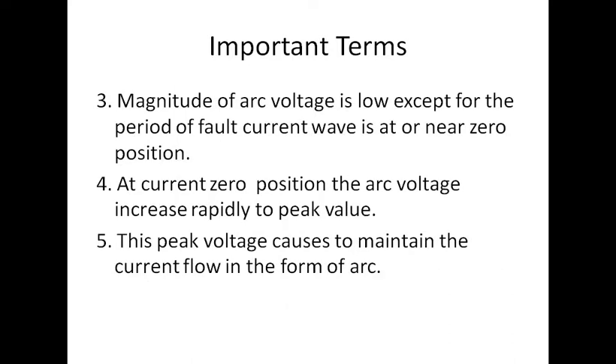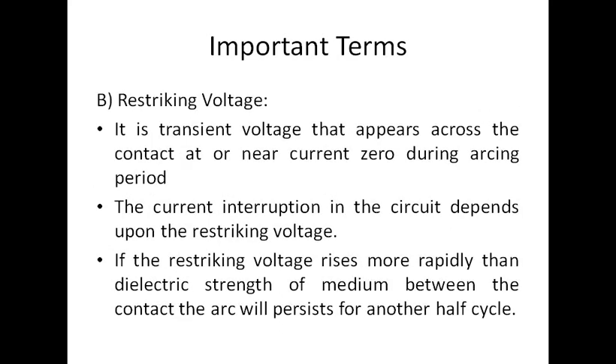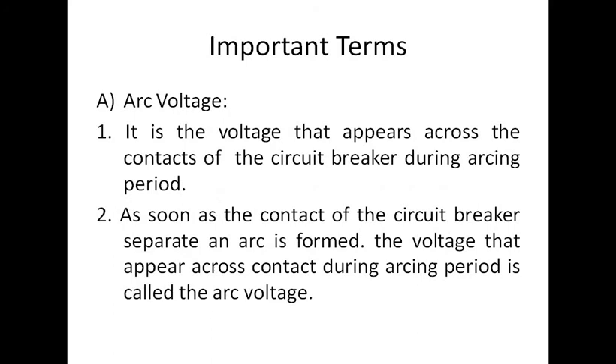The magnitude of the arc voltage is low, except for the period when the fault current wave is at or near zero position. At the current zero position, the arc voltage increases rapidly to a peak voltage. This peak voltage acts to maintain the current flow through the full arc. When the contacts get separated, the arc will form between them, and the voltage responsible for maintaining the arc is known as the arc voltage.